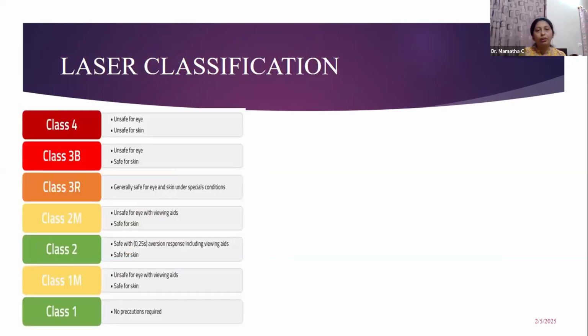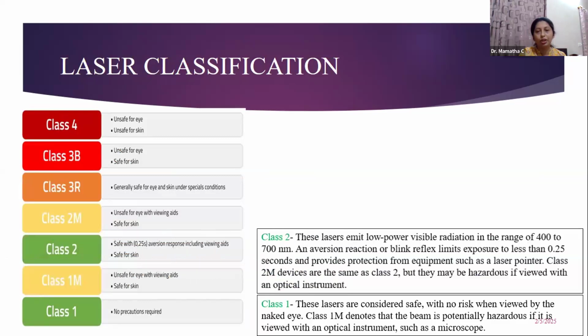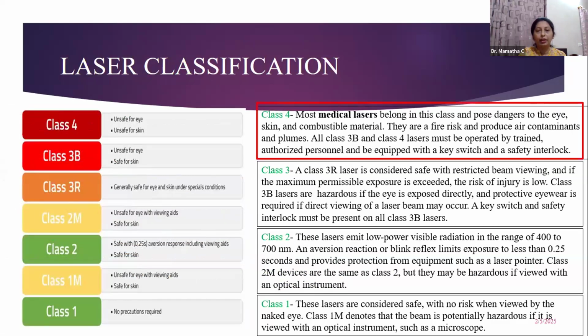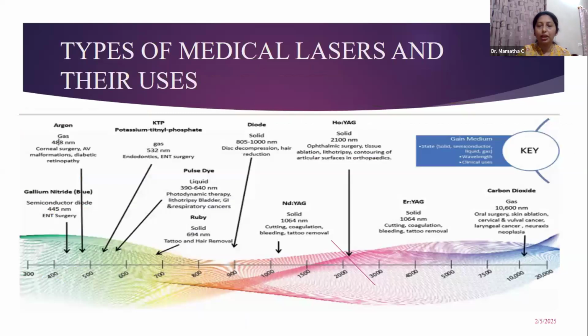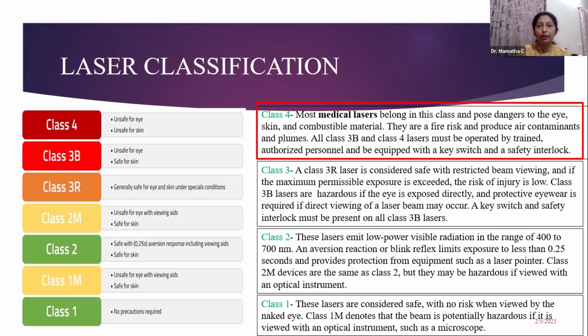Let's see how lasers are classified. Lasers are classified based on their wavelength, power, and their potential to cause injury to biological tissue, into class 1 to class 4. Our medical lasers belong to class 4, and they pose danger to the eye, skin, and combustible materials. They are a fire risk and can produce air contaminants and plumes. All class 3B lasers and class 4 lasers must be operated by trained, authorized personnel and must be equipped with a key switch and a safety interlock.